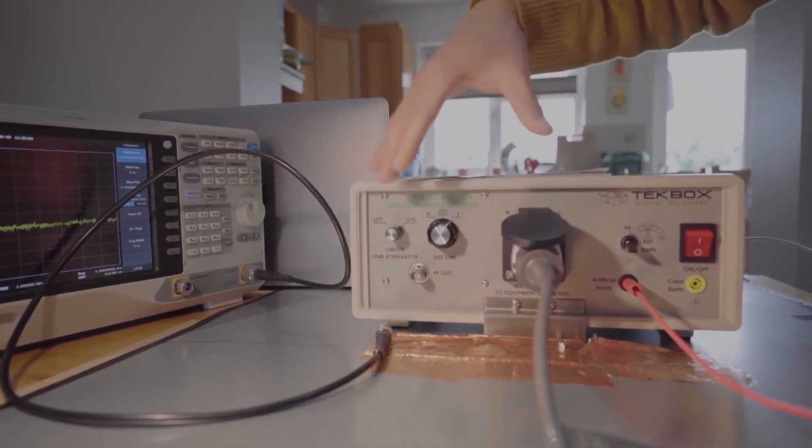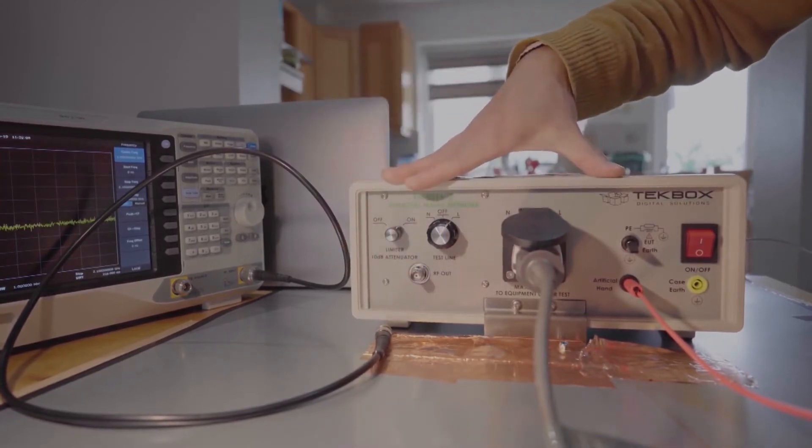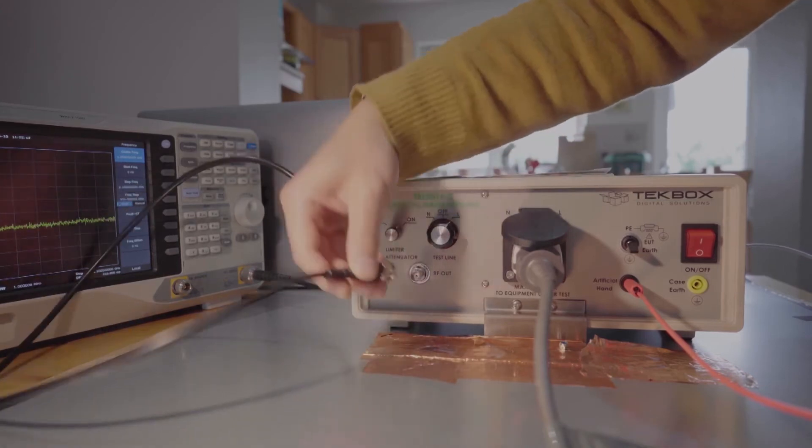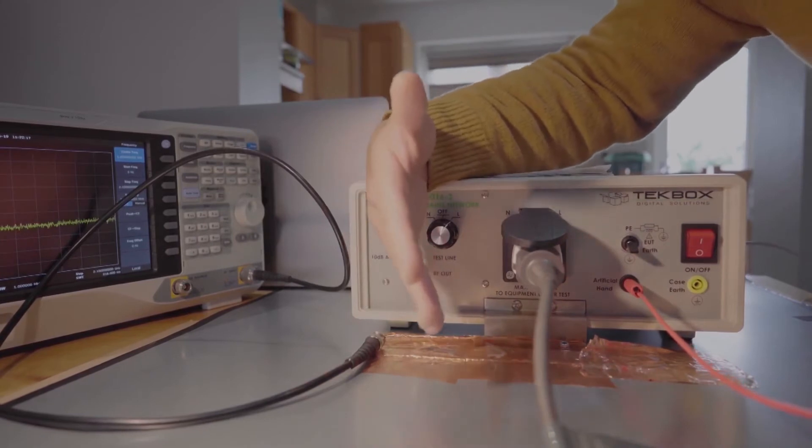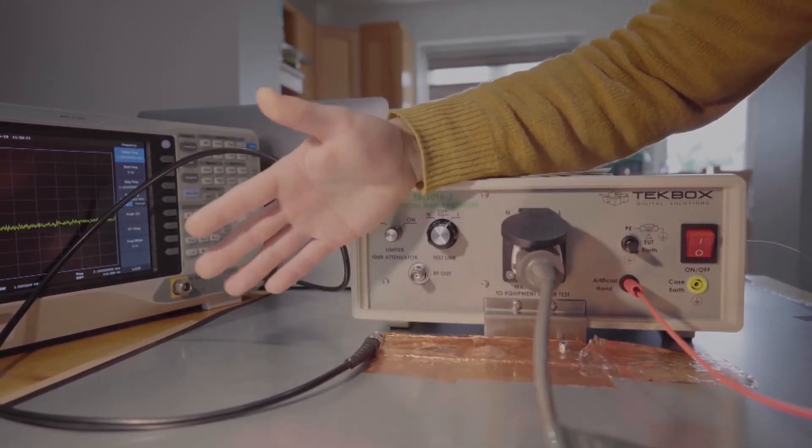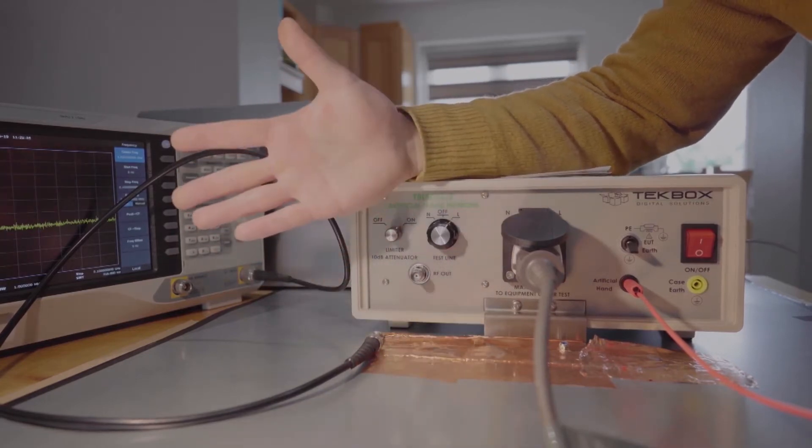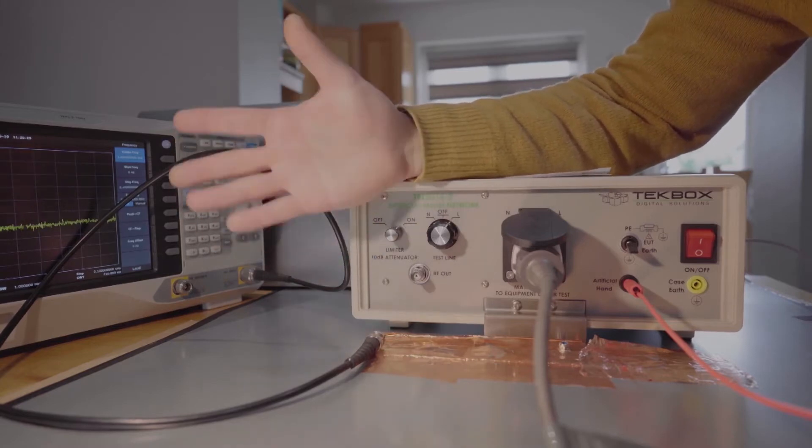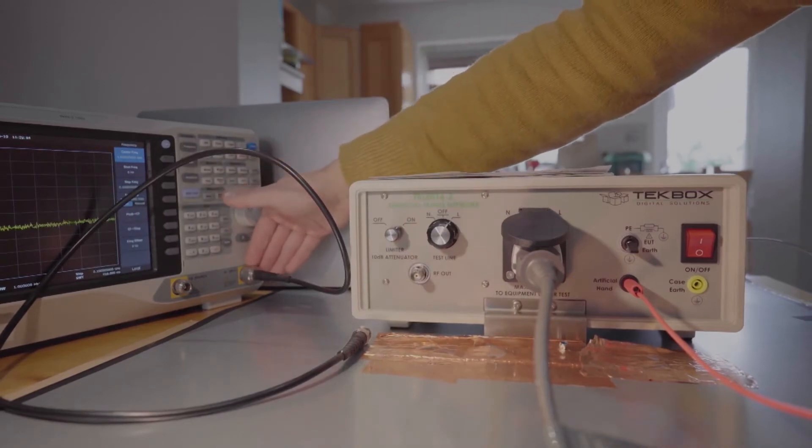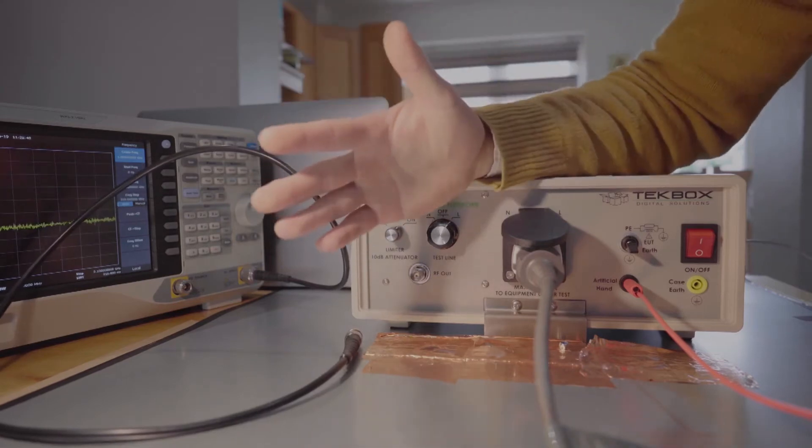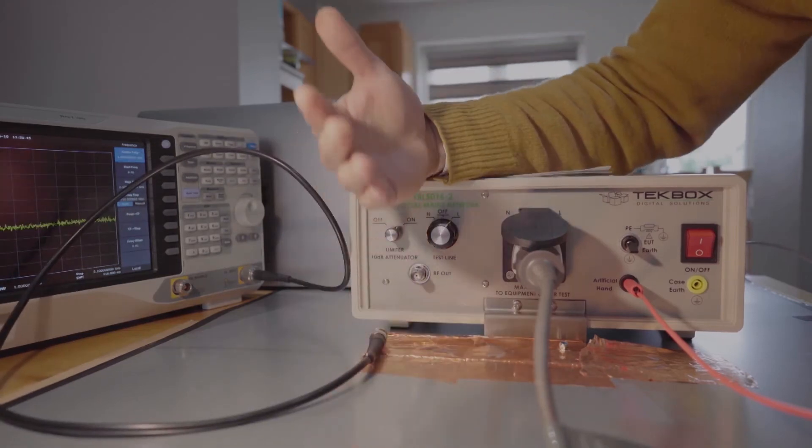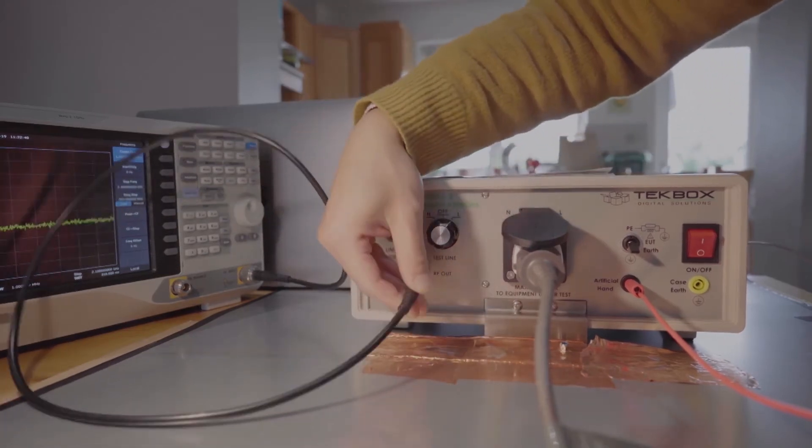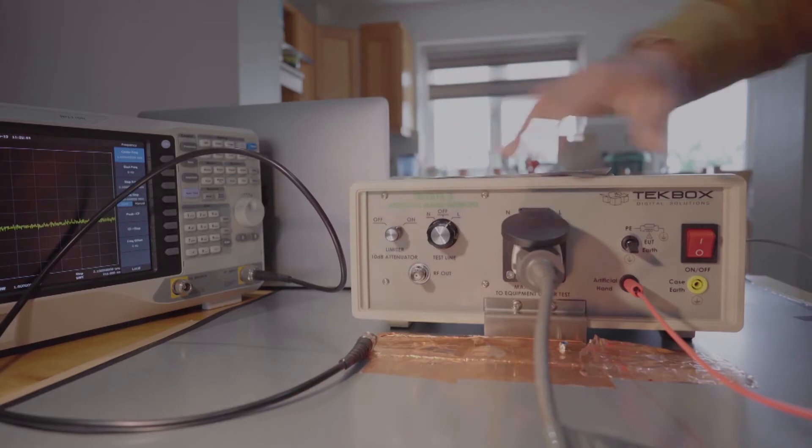You need to check the output of the RF out of the LISN. First of all, check whether the voltage level is within your spectrum analyzer RF input. Any voltage level higher than the specified inputs will damage the RF input or front end of your spectrum analyzer. Even if I measured the RF out of the LISN idle in idle state within the limit, I'm not going to connect it until I run my product. The product on test can be highly inductive, so when you switch it on or off there might be a very big kickoff voltage or back EMF that can damage the front RF input.